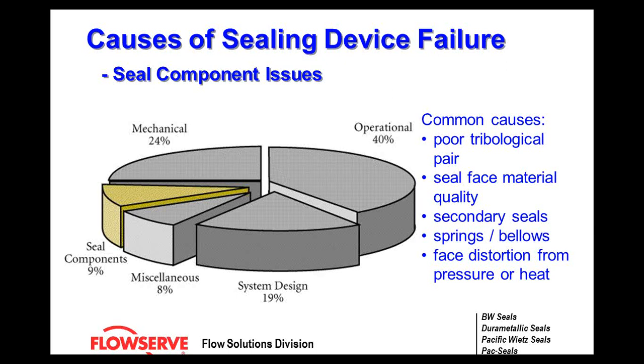The seal face material quality — making sure you have the proper seal materials for the application you're running. Secondary seals, which are the gaskets and o-rings, must be properly selected for heat and chemical attack. Springs and bellows: springs can get clogged; bellows, if they're the wrong metallurgy, can get corroded. Face distortions from pressure or heat are also an issue — a mechanical seal under great pressure will actually bow and the profile will get distorted, causing a leak.